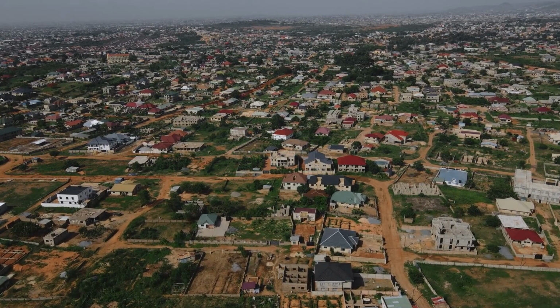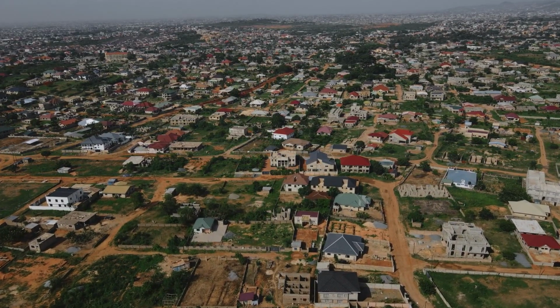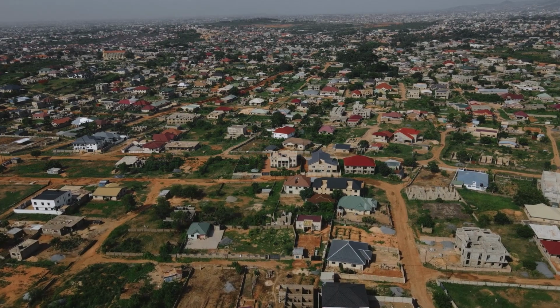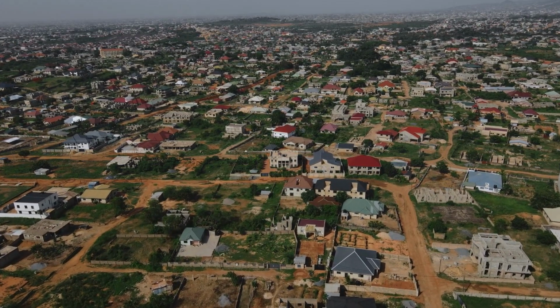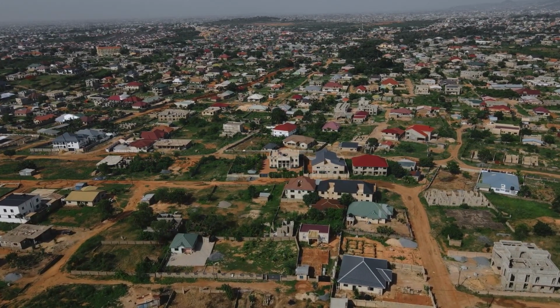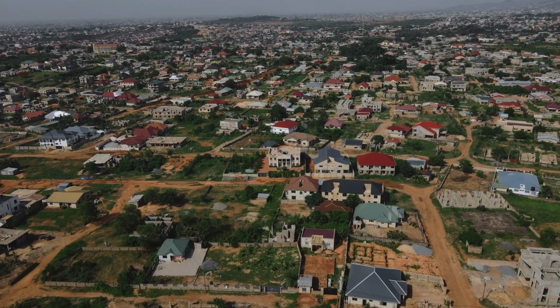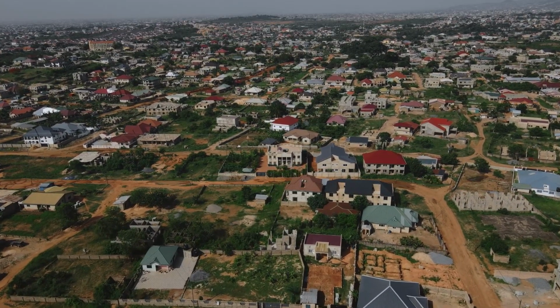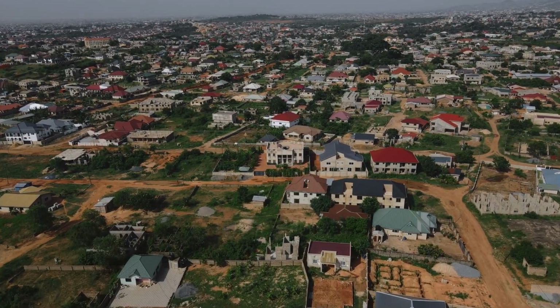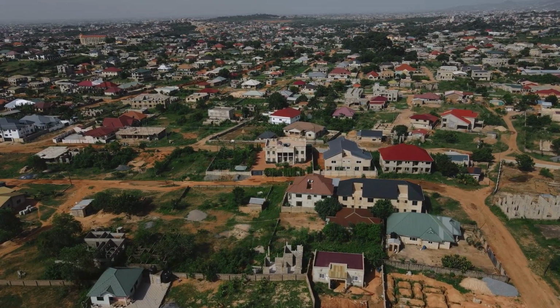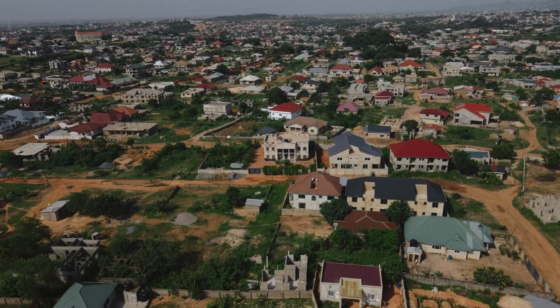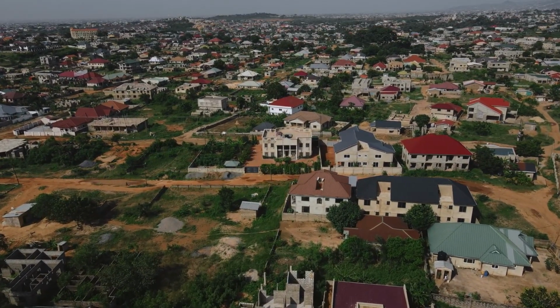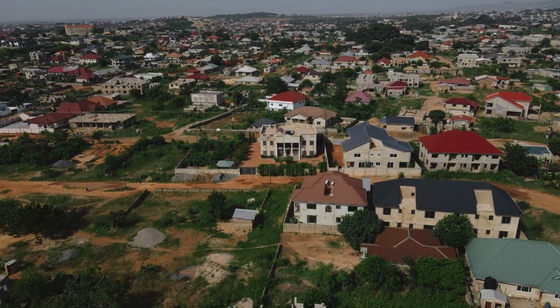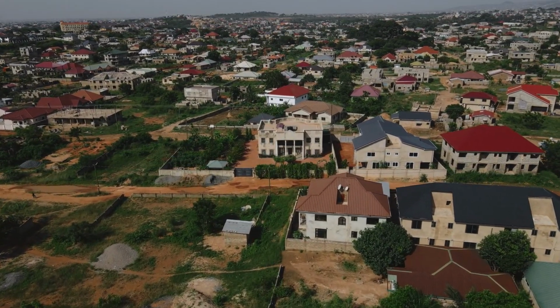The house was a 4-bedroom property with a 3-phase electrical supply. The installed AVR was rated at 50 kVA 3-phase. Immediately I was skeptical — for a house of that size, a properly designed 50 kVA 3-phase AVR is normally more than adequate. So before recommending thousands of dollars of new equipment, we decided to investigate properly.